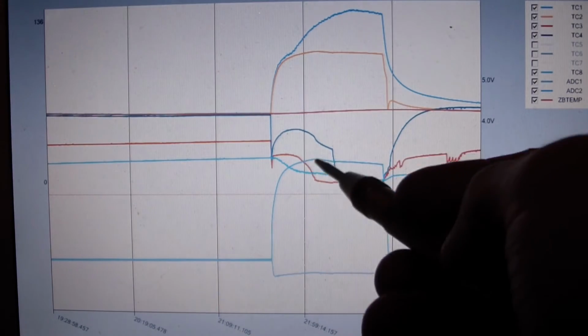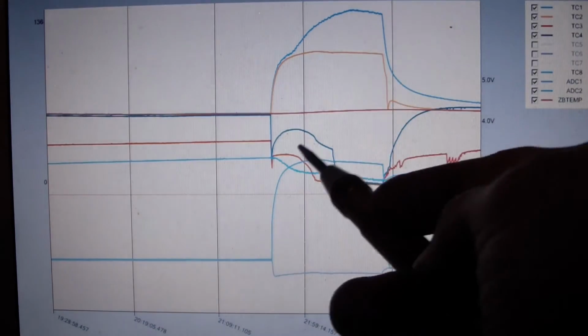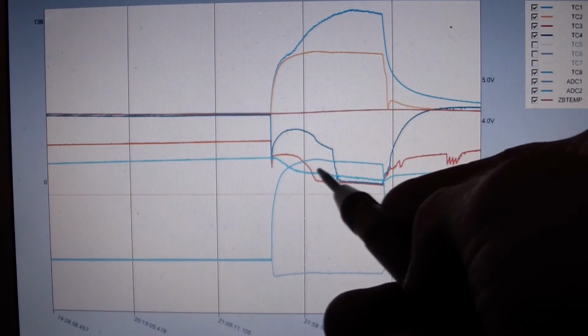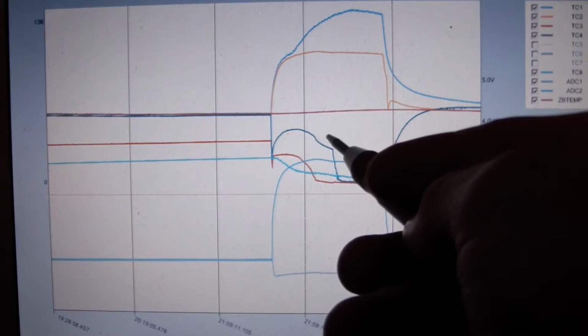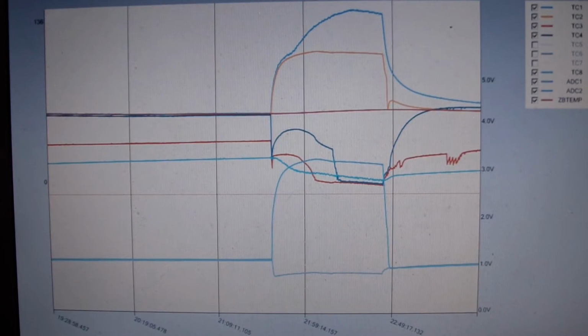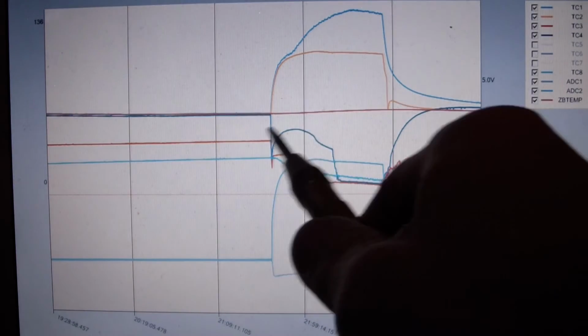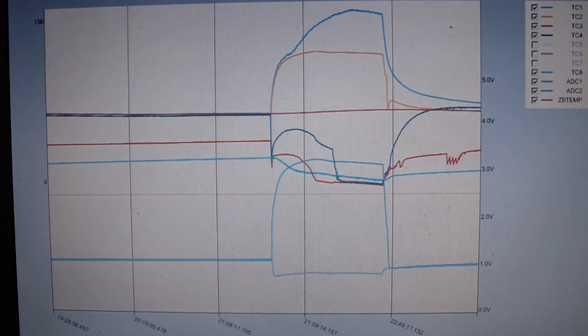And correspondingly we also see a slight drop in suction temperature there right after the evaporator. And also we start to make a little bit of headway on the one after the heat interchanger, because before this time it's adding heat. Well, it's adding heat at the heat interchanger all the time.